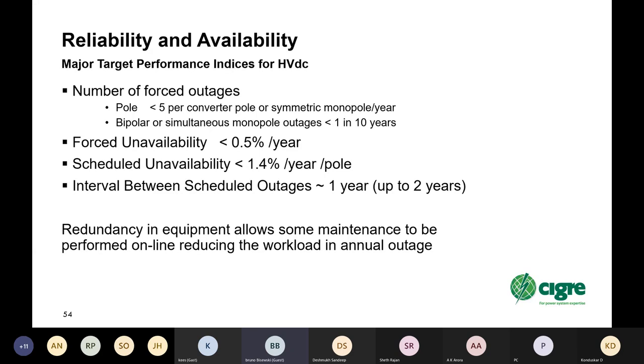And interval between scheduled outages, typically 1 year. With LCC, you can sometimes stretch it to somewhat longer, maybe even 2 years, but it depends on failure rates and how much maintenance you can perform online, and thus reduce the workload in the annual outage.